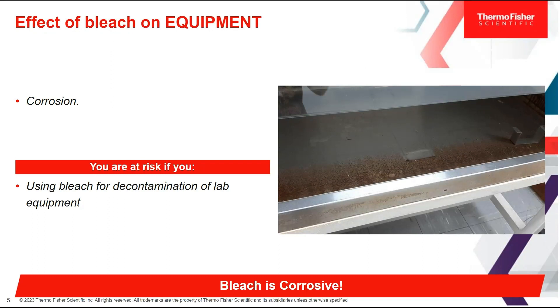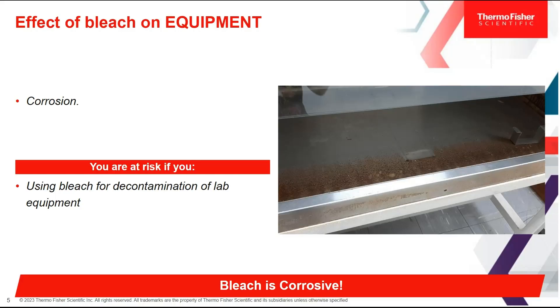The third effect relates to bleach on equipment. Bleach is often used to disinfect equipment, but in many cases it can actually lead to corrosion of metal. We work with a lot of stainless steel in the labs, and you have to read your user manuals carefully to understand the recommended cleaning agents. In many cases manufacturers may recommend not using bleach due to its corrosive nature — equipment such as biosafety cabinets are a common example.